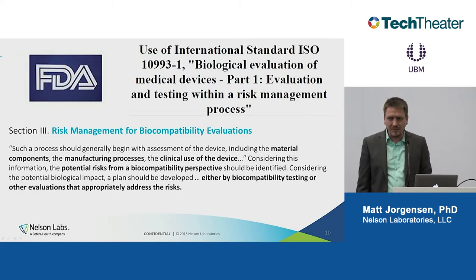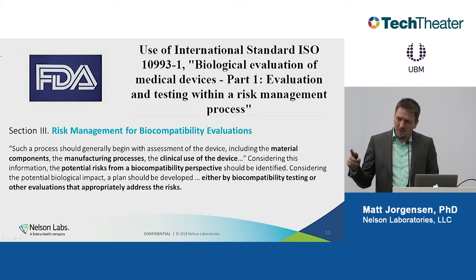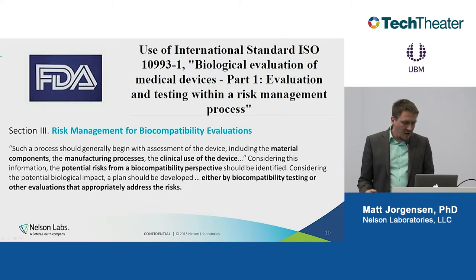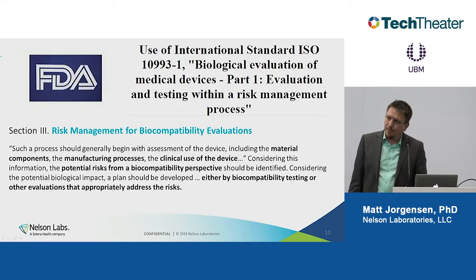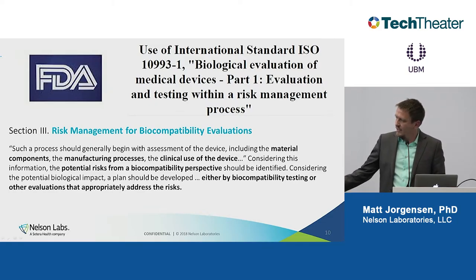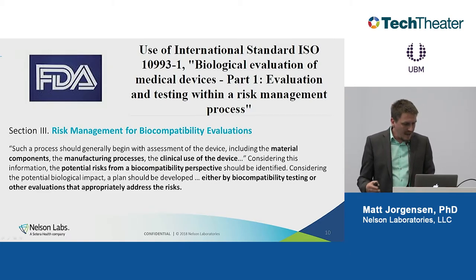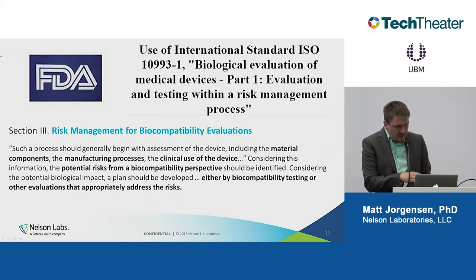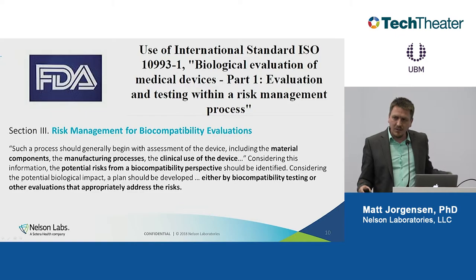So in their draft guidance on the application of ISO 10993-1, it talks about this risk management process for biocompatibility evaluations. That's really the whole theme of this, that now we're using this risk-based approach. If I can just read that excerpt from their document, it says such a process should generally begin with the assessment of the device, including material components, manufacturing processes, and clinical use of the device. So this is where you should start.